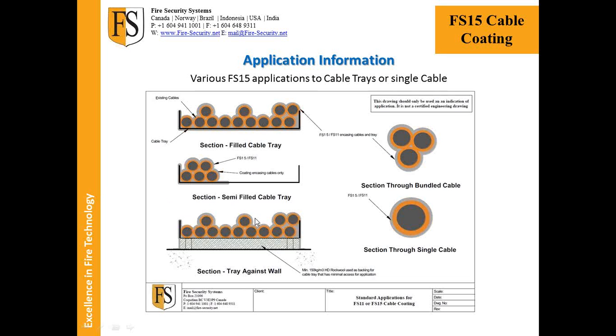And you'll still have complete heat dissipation out of the sides and the top of that tray. But we have to do this because there's no way that you can physically get even sometimes your hand to the back, even with a handful of coating, to put on the back of the cables. The area is just not possible, so we put rock wool down behind, and that gives protection to the back of the cables. And you put FS15 on the side of the rock wool panel? Yes, that FS15 comes all the way along, down and across. Mm-hmm. So it always does, because FS15 is completing and sealing that whole system from flame spread. Yeah.